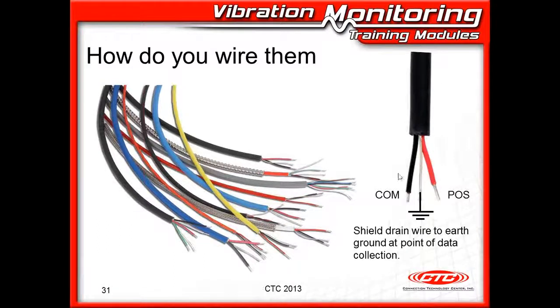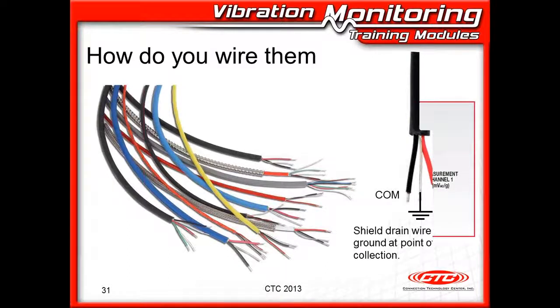However, it's not just the shield and the protection it offers. You have to take that shield drain wire and you have to take it to an earth ground at the point of data collection. It's very important that you get that to an earth ground so that you can take that noise away and bleed it off to earth. And then naturally you have your positive conductor and your common conductor here shown as the red and the black wire. But very important to get that shield drain wire grounded at the point of data collection. Remember, we've got the sensor isolated, so we've got to ground the data collection end.